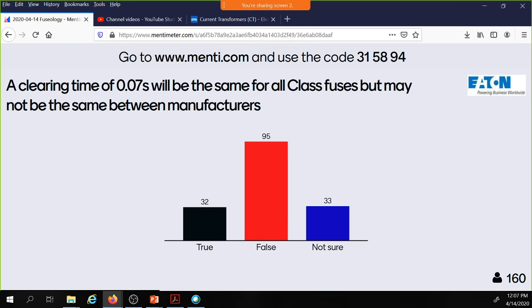Now, let's ask why 0.07 seconds. Well, if you were in some of the classes for the code changes, I think one of the earlier ones, if you were in my hazardous or arc flash, I did 2 sessions on incident energy reduction. 240.67 is a new requirement in the National Electrical Code. It was new in the 17 code with an enforcement date of January 1st, 2020. And 0.07 seconds is a key number: you have to have a clearing time of 0.07 seconds or faster at the arcing current to meet that section of the code and not require an additional arc reduction technology.